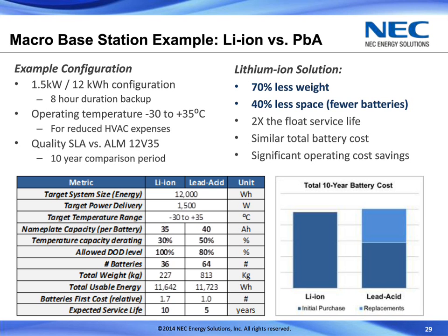So getting 10 years with lithium as opposed to 5 with the lead acid, that really swings the cost in favor of the lithium. So for this case, we end up with 70% less weight, 40% less space, twice the float service life. The cost ends up similar, but the lead is slightly higher. And there are significant operating cost savings, which were actually not factored in to this bar graph that you see here.